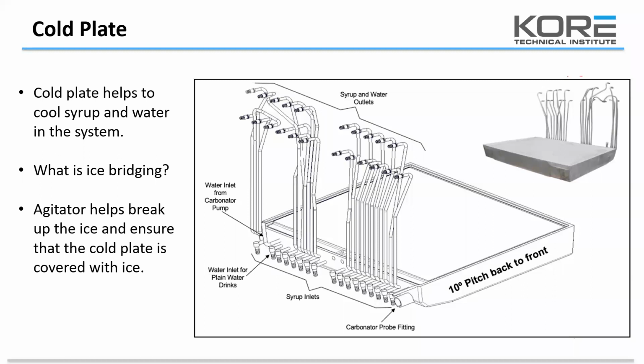The agitator helps break up the ice and ensure the cold plate is covered with ice. We want to make sure there is ice all the time on that 4-inch cold plate. It's going to play a factor in how your beverage tastes, and it also helps with brixing. If we don't have ice on the cold plate and go to brix it, we're going to have issues - you can tell when there's something going on when you do a brix. It wouldn't hurt to test your product with a thermometer to see the temperature coming out. Like we said before, it's about 36 degrees is what your product should be dispensing out of these fountain machines.